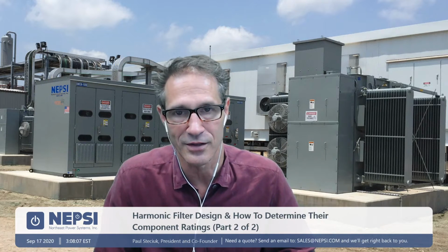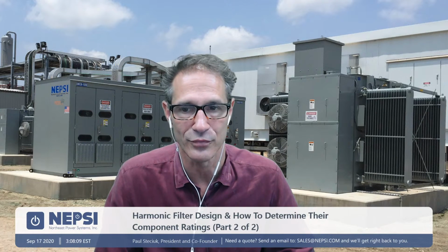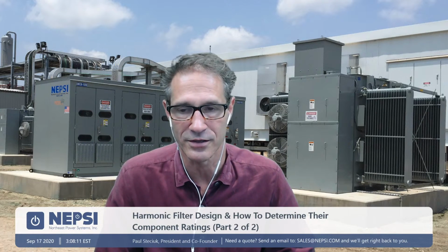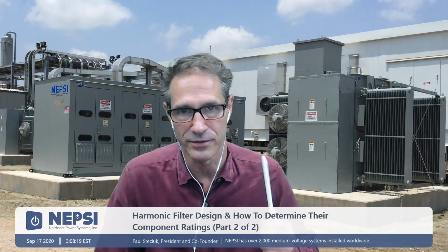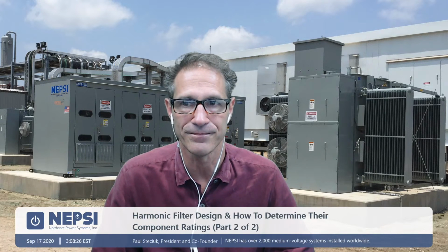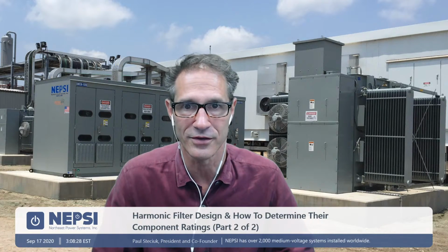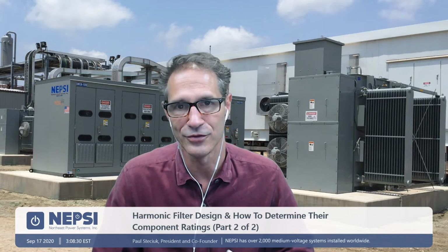even resistors that are connected incorrectly. We will be able to see those things. Maybe a missing neutral within the capacitor. So it's really a very important test that all EPCs should be specifying. If you really want to make sure that your filter meets the specification, that it is going to do what your study says it should do, then you should be specifying SFRA testing on all harmonic filter systems.